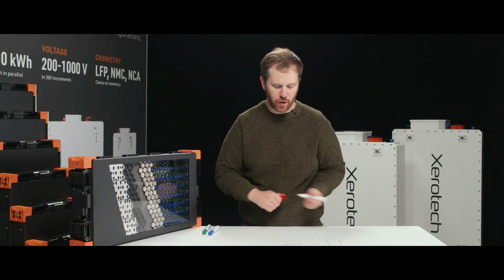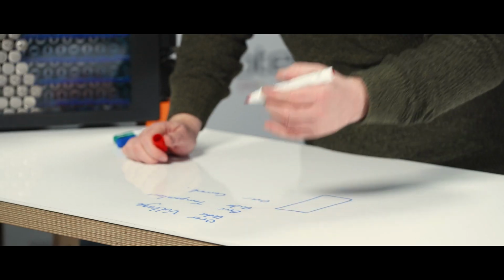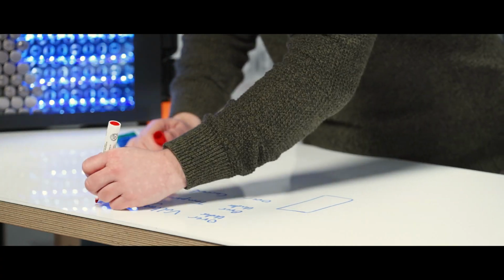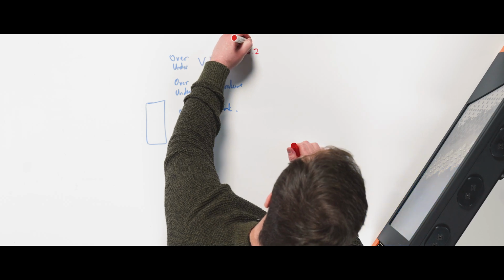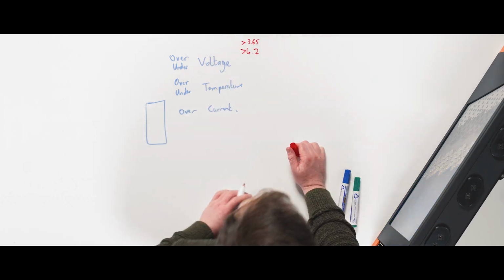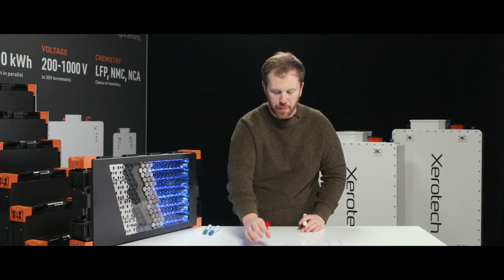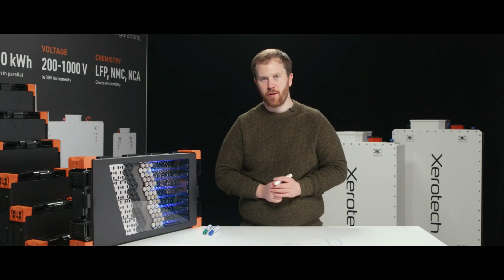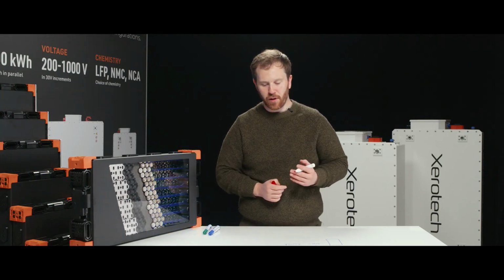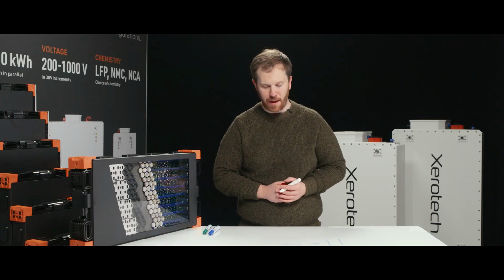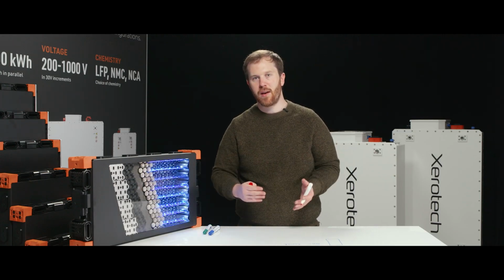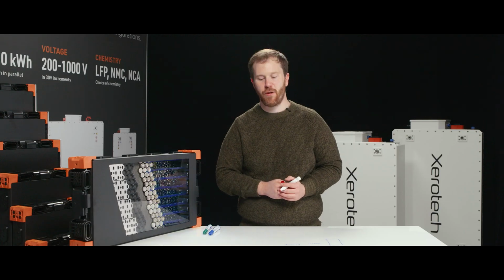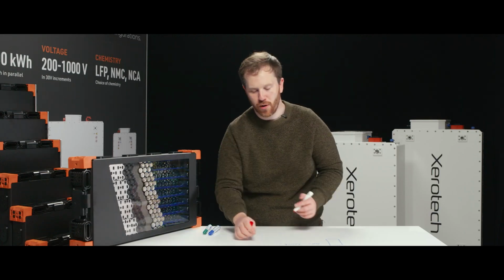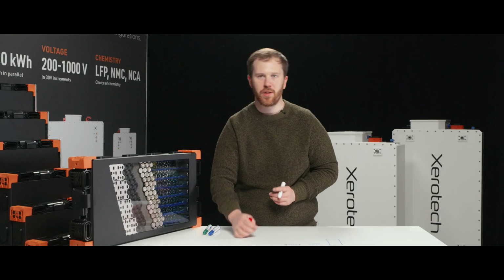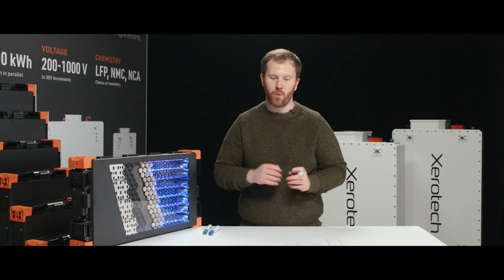So when we look at voltage, over voltage for the vast majority of chemistries is more than 4.2 volts. Or for LFP, it's over, say, 3.65 volts, above their charge limits. This is really, really bad to overcharge a battery. It can result in irreversible electrochemical damage. It can result in excessive heating, gas generation, fire, many other factors. Big no-no in terms of overcharging of battery cells. So that's a critical one to do.